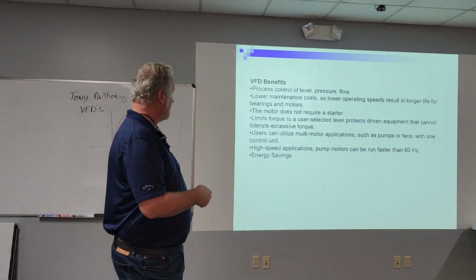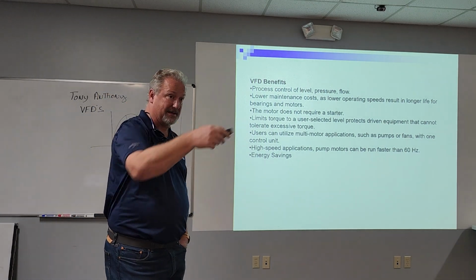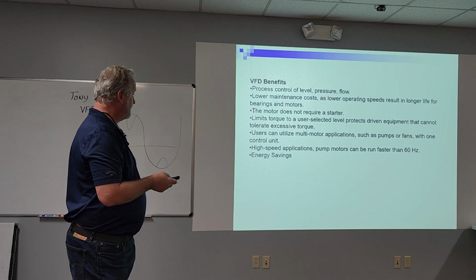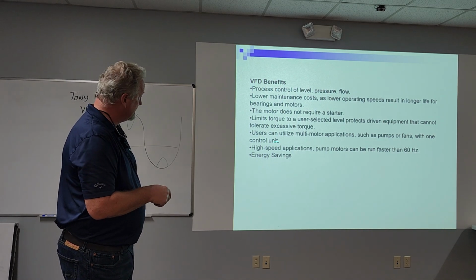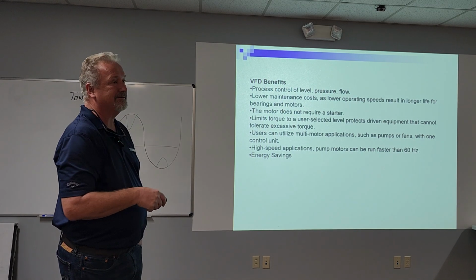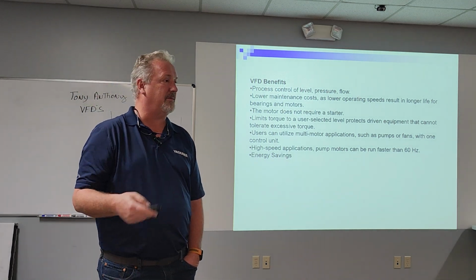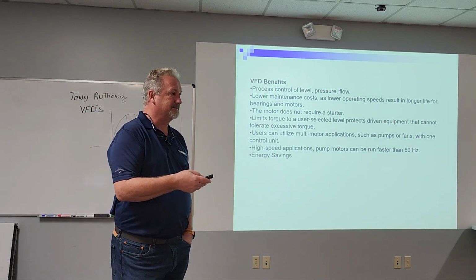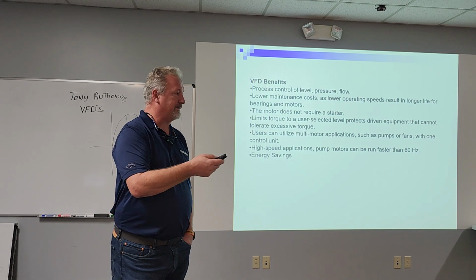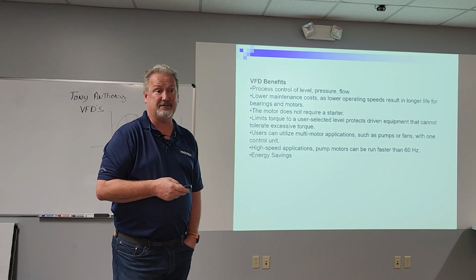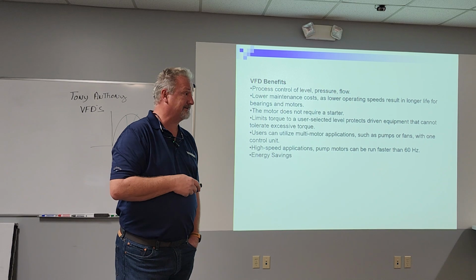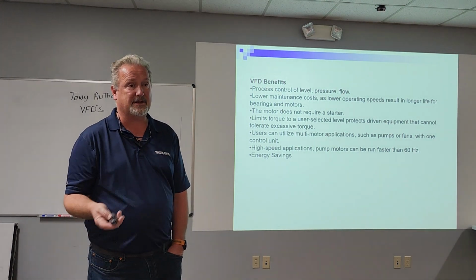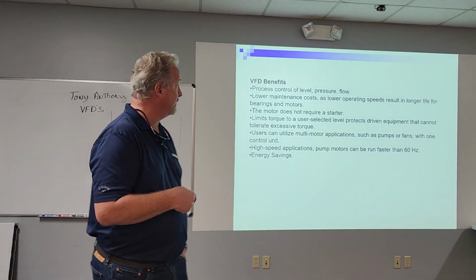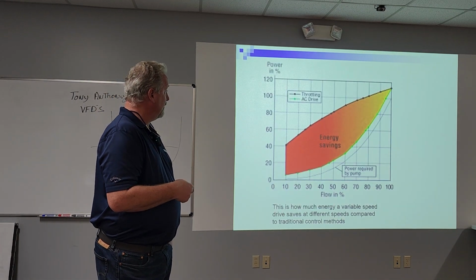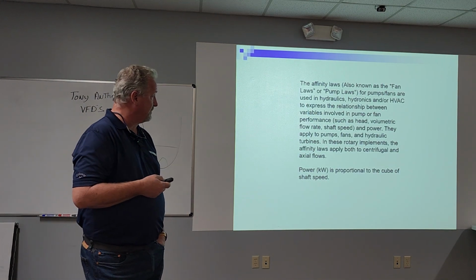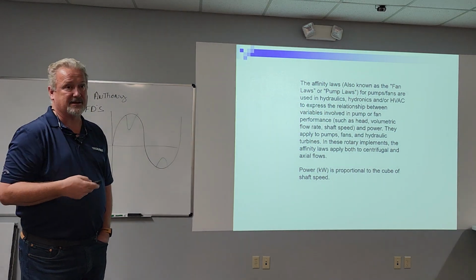So there's a lot of different things we can do. We can run high-speed applications. Sometimes your guys want to overspeed them, go faster than 60 hertz. But the number one reason we see it in a lot of applications is right here: we can save a lot of money. The payback time on most drives, if you can slow it down to 40 or 50 hertz, somewhere in that ballpark, is usually less than a year. And now they're putting that money in their pockets. There's software out there that can show that payback analysis, and it's really good software. We've already discussed energy savings and the affinity laws, which is what we're talking about. That's the cube of the speed.